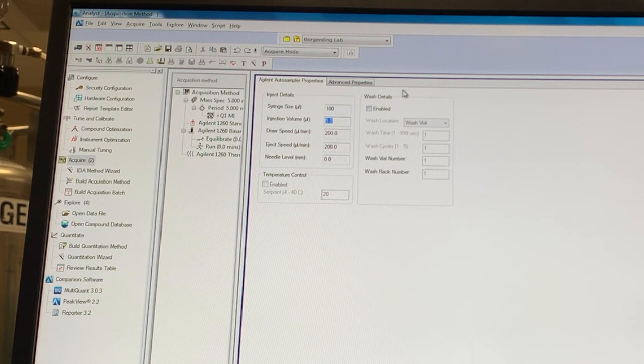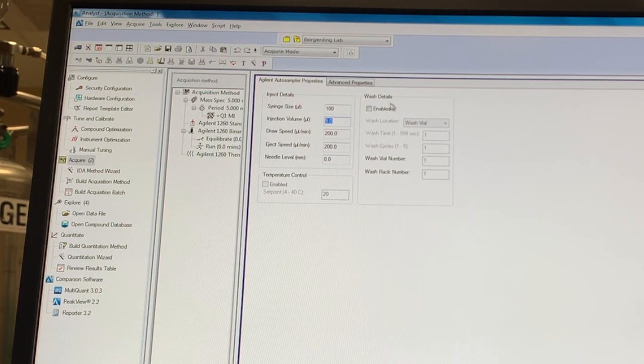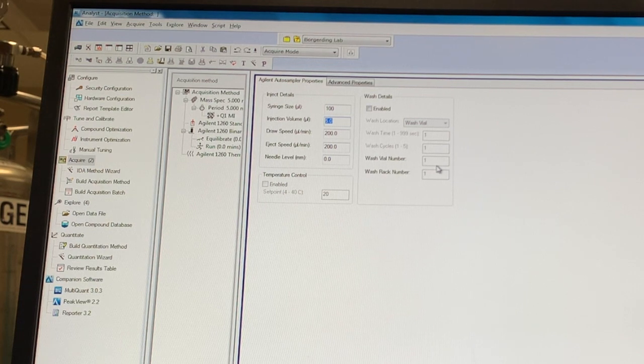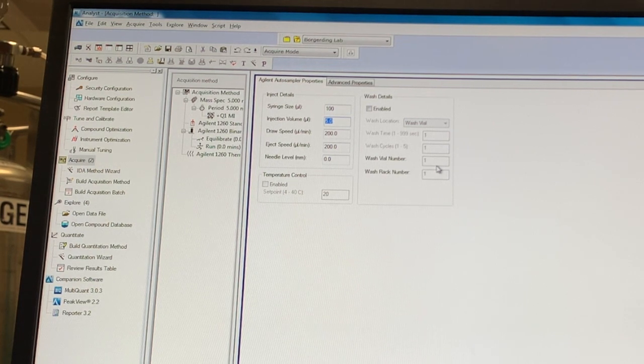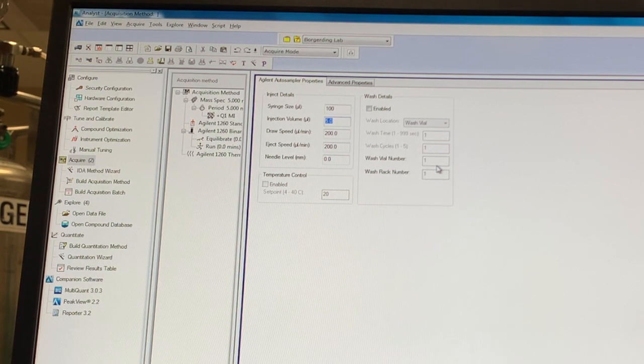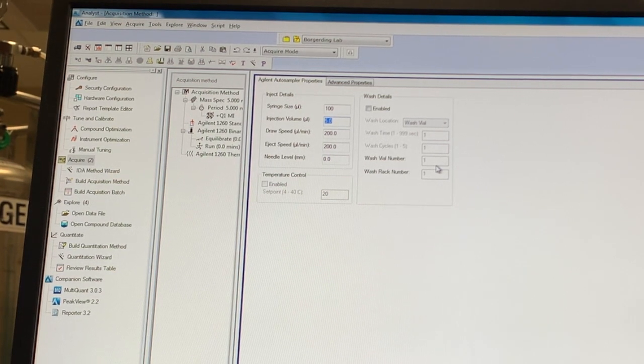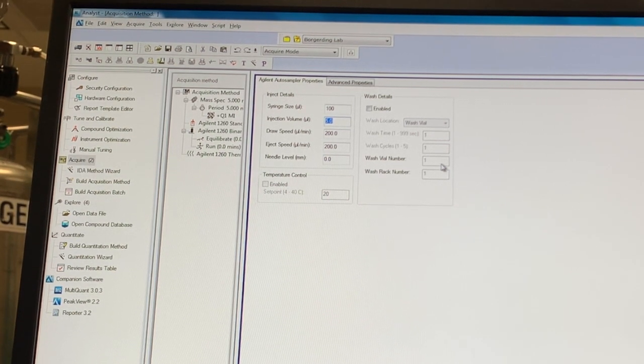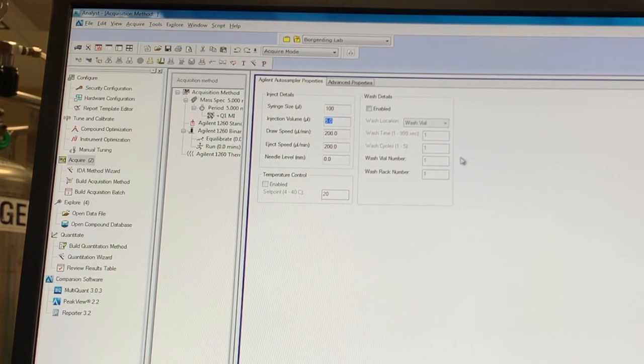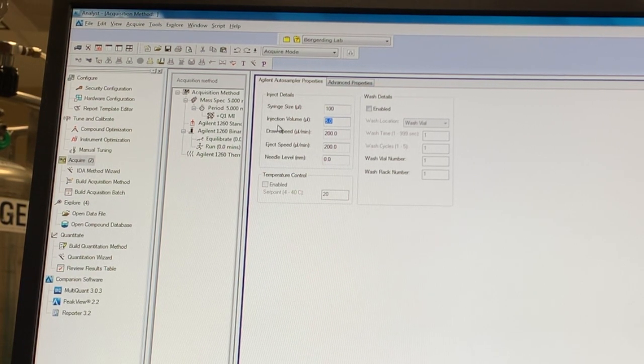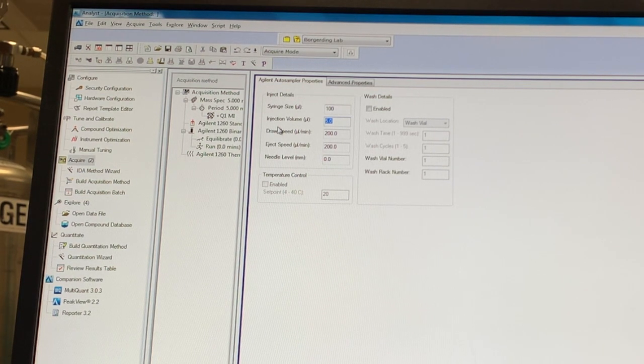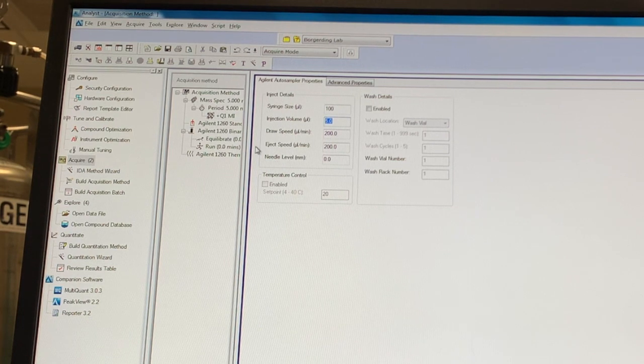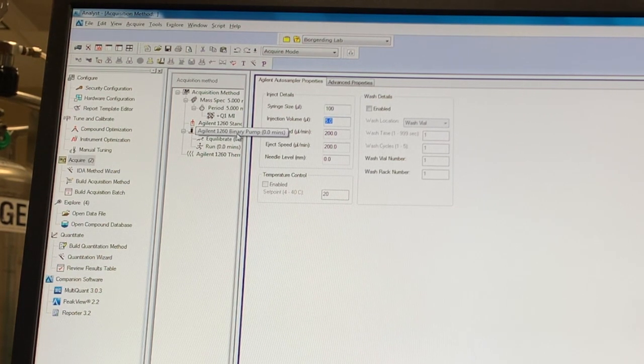And then you can also enable some wash settings. There's some predetermined wash settings where you have to enter a vial that you want to, if you have like a, say, an ethanol or acetone rinse that you want to rinse your needle with, you can enter where that is on the auto sampler. And the auto sampler will then, after injecting your sample, pick up a little bit of this cleaning solution just to make sure that the needle tip doesn't get clogged or you're contaminating any of your samples with that needle.